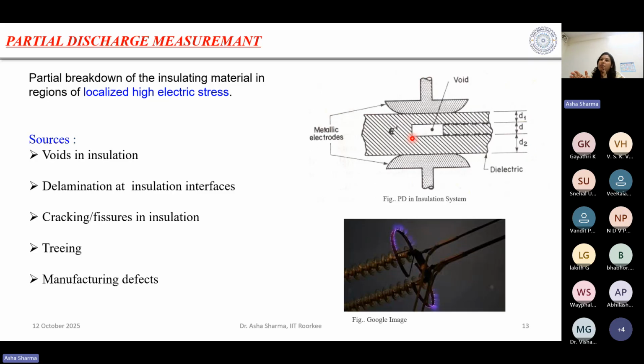The material which has the lesser permittivity is stressed more. So what happens? On the outside, what am I seeing? Across the insulator string, I am applying 11 kV, so it must be able to sustain that 11 kV. But due to the air bubble or any defect present within the insulating system, it may experience higher electrical stress within itself. Across this I am applying 11 kV, but within the string it may experience more than that because of the difference in the permittivity present in the system, and it may break down. If I look through the naked eye, maybe I am not able to see it, but after a certain time, if the breakdown of the internal void or internal cavity happens again and again, it may cause the complete breakdown.